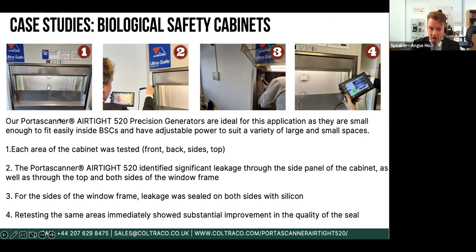These, as I say, they contain very harmful chemicals and pathogens, and so often need to be fumigated at regular intervals. During the fumigation, it's very important that the fumigant is contained in the cabinet, so it needs to be able to maintain a certain level of negative pressure. And as this is a structure with an open front when it's in use, so that the users can get their hands into to perform their tests, this is not something that can be tested using pressurization equipment. In fact, currently, the only way to test this at all is to use an aerosol spray to produce particles and a photometer to detect those through any of the seals.